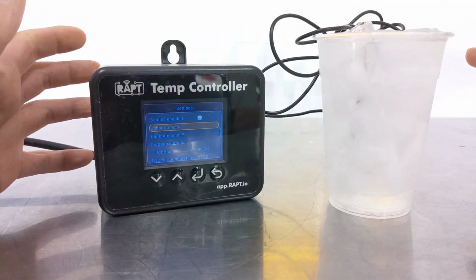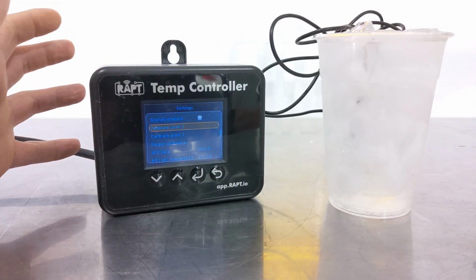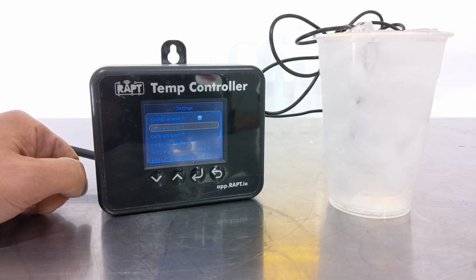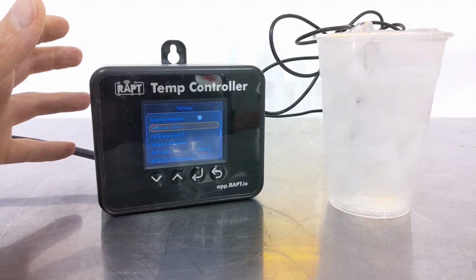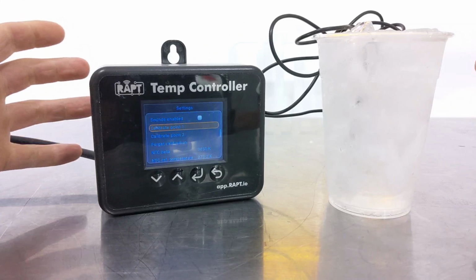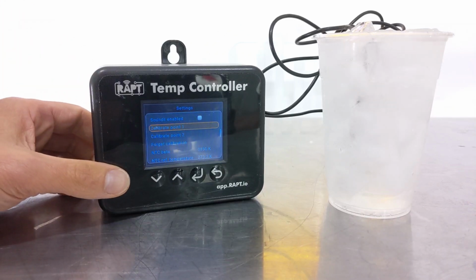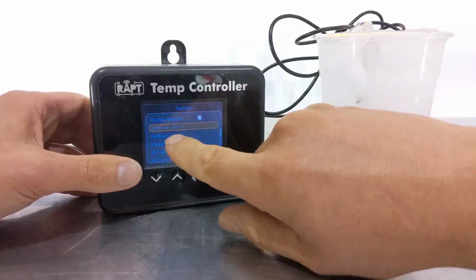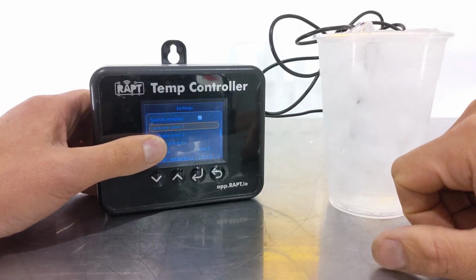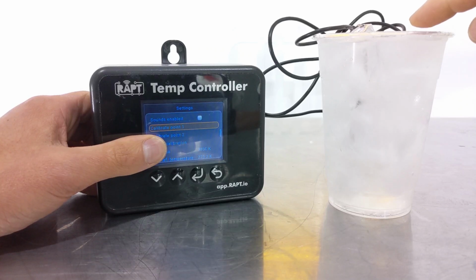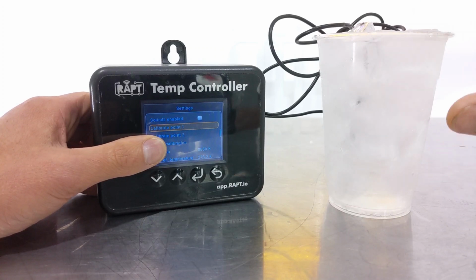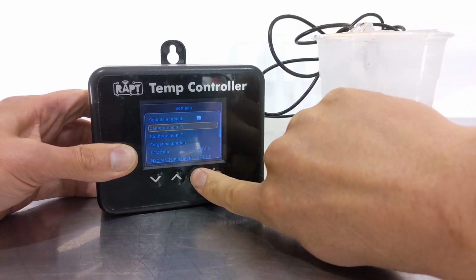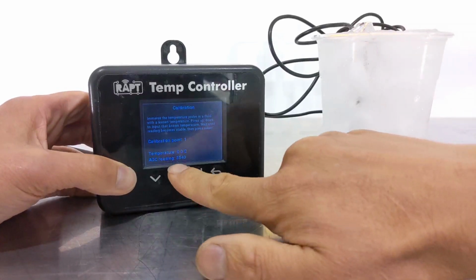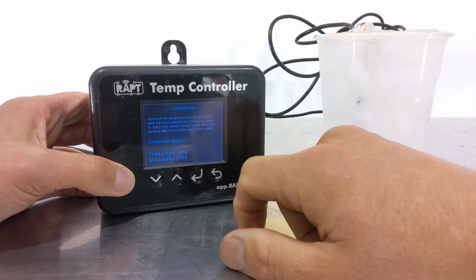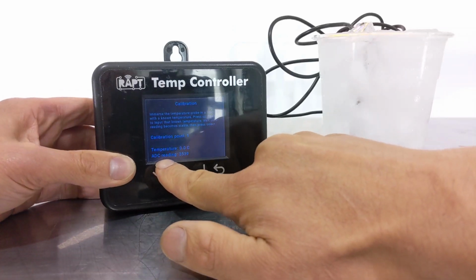Now, in reality, if you don't have a high accuracy probe, then you're just going to have to use the freezing point of water and obviously the boiling point of water, which are the two easiest points of calibration because they're very well known, even without having to go out and buy an expensive thermometer, for instance. So with calibration point 1 here, I'm going to do that one first. So I've got this probe sitting in the ice water. Now notice this plastic cup here is absolutely chock-a-block with ice. I couldn't fit any more in the cup. I've already had the probe sitting in there for a while. So what I've got here is 0.00 degrees Celsius. And what I'm looking for is the ADC reading here.